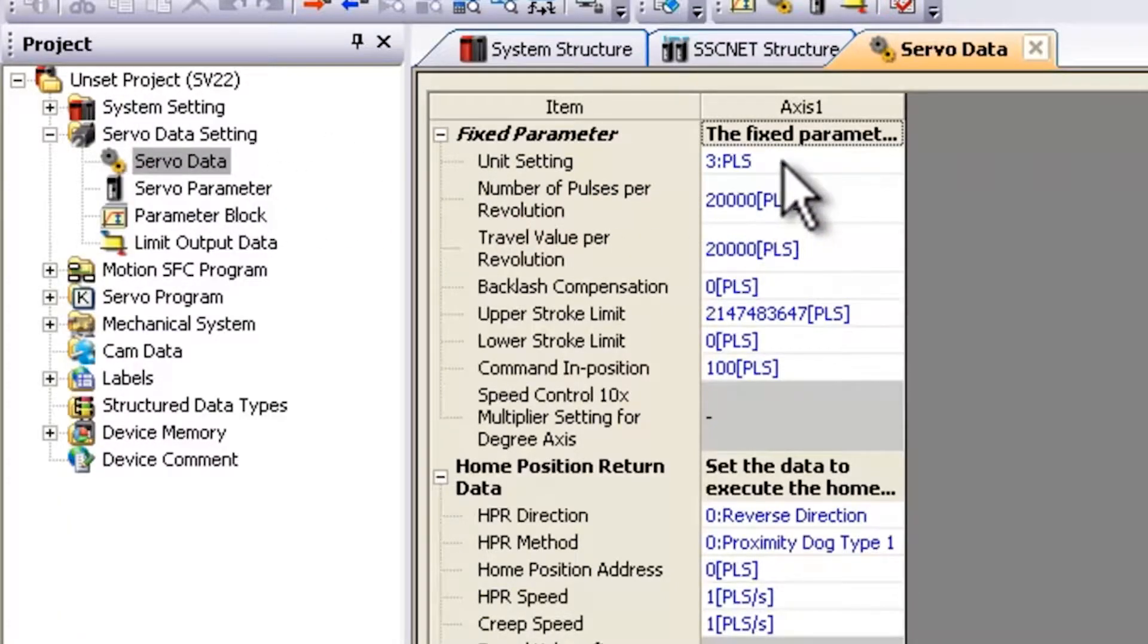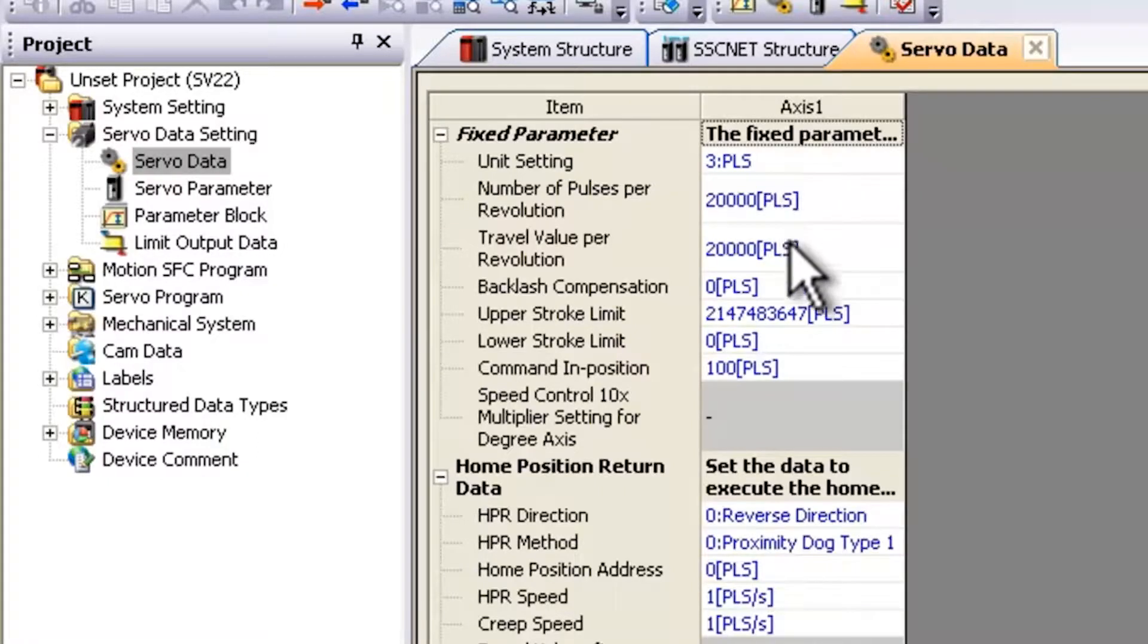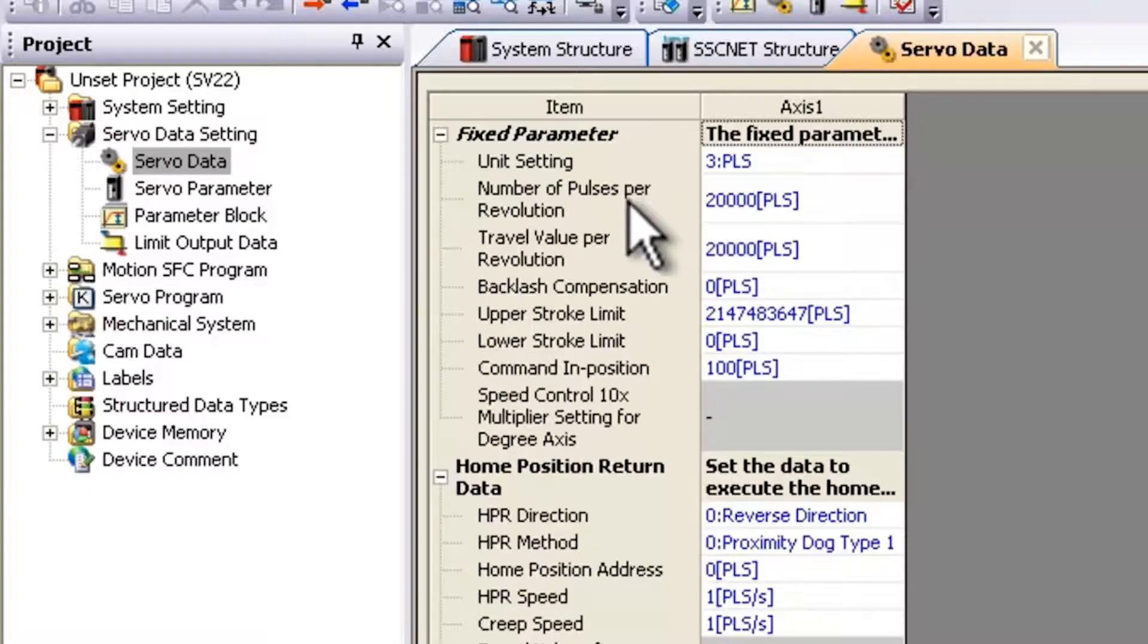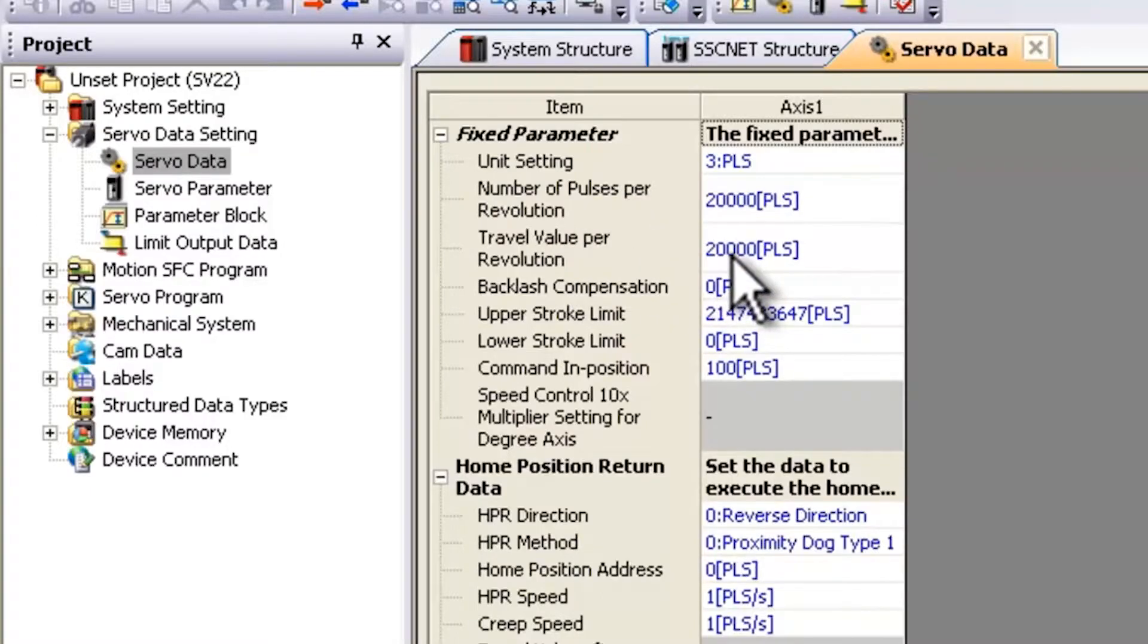So if I double click on this area, you can see where I would set all of my various unit settings, pulses per revolution, my travel per revolution. Keep in mind the pulses per revolution and travel per revolution relate to the load that's moving.